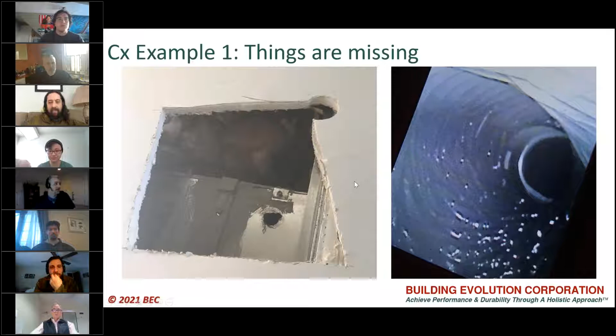So moving on to what is actual. Well, a few things had changed. The fan coil unit is now going out this direction, doing a hard right. And all those volumetric dampers that you see, I put the big X's over them, they don't exist. And when we actually did measurements on it, bedroom 1, there's no complaints. So with the 94% of the airflows, 6% low.